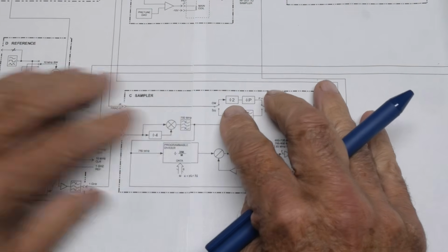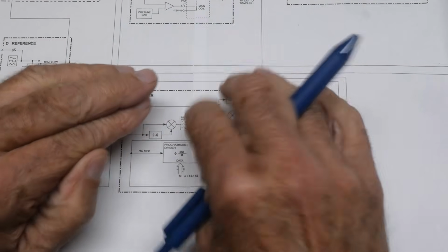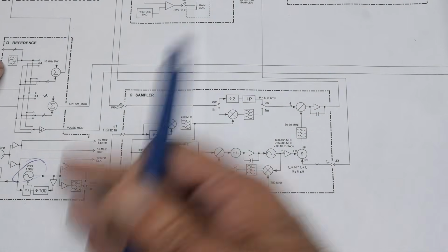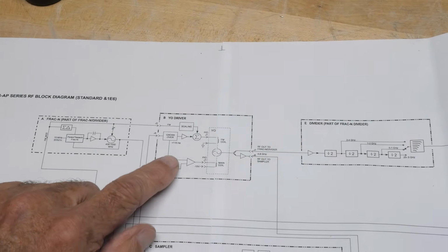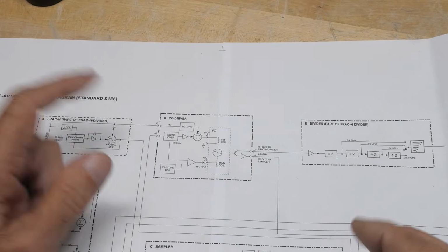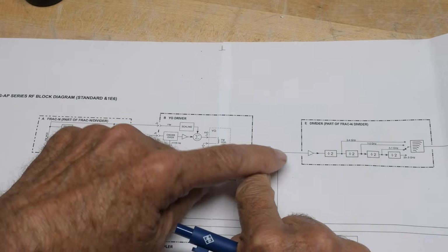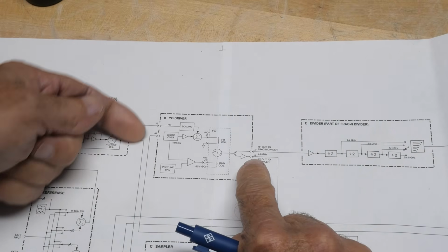And it's going to sample that 4 to 8 gigahertz, and it's going to compare it to something that we digitize, and we make an accurate thing, and we compare it to the output. And we want these things to match, and then the error voltage, whether it's too high or too low, if it's too fast or too slow, we're going to feed that back into the YIG driver. So the function of the sampler is to look at the output, measure it, and then give feedback to give you the correct voltage, okay?